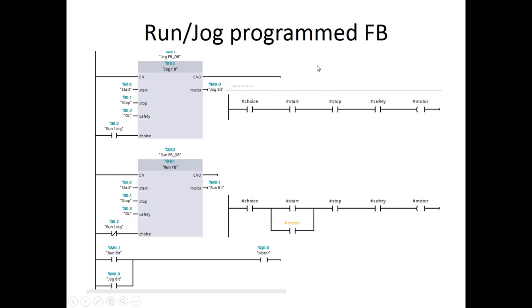The next example: I took the run-jog routines and unconditionally scheduled them. See this right here — the EN is true, this EN is true. So both of these subroutines are being called and they're both running. That's different — last time we used the run-jog to either schedule this one or schedule this one. This time we still have the run-jog wired in so we get true here and false there, or false here and true there, but both subroutines are automatically running.